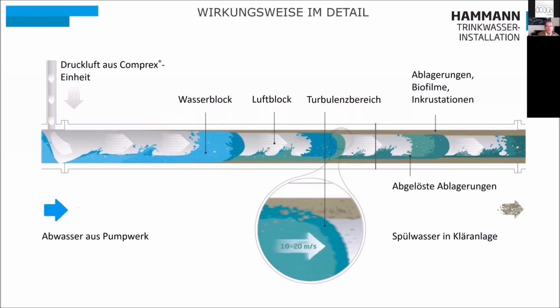From the left in this picture, little water is coming in. We relieve the pressure from the system and open 2 or 3 taps on the other side, depending on the nominal width, to release the pressure. When we then inject air at a defined and carefully measured pressure and quantity at an injection point, as we will see later in the demonstration, it will first displace the water in the system, pushing it out of the way.